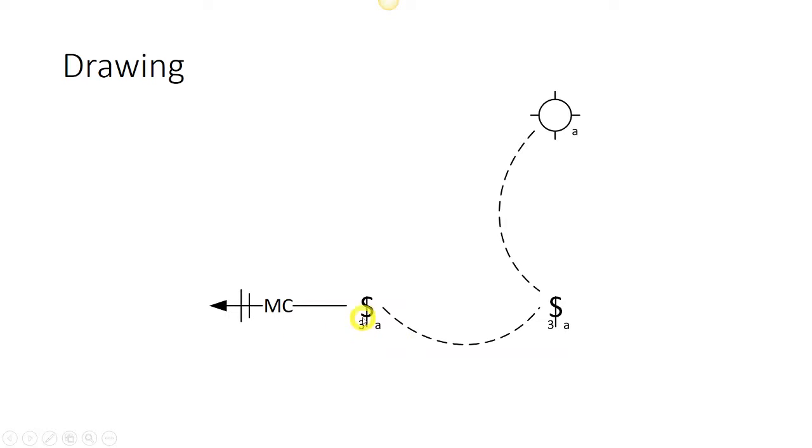We're familiar with a couple of these symbols. This right here is our home run, or where we're actually going to get our power from for our circuit. We have a switch in this location and a switch in this location. Now there is a little bit different nomenclature on this switch. It has a number 3, which is new to us. That means it's a three-way switch. We'll be talking about that in future slides. And then we're going to ultimately be controlling a light. So the A next to the switches means that it's going to control this light that has the A next to it.